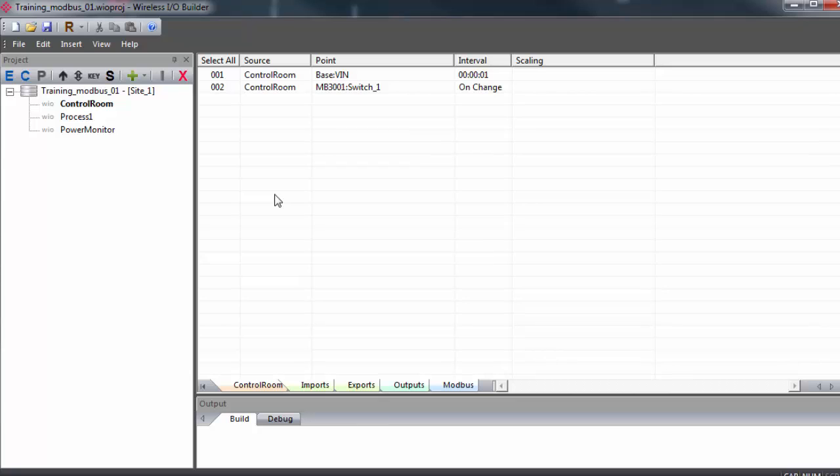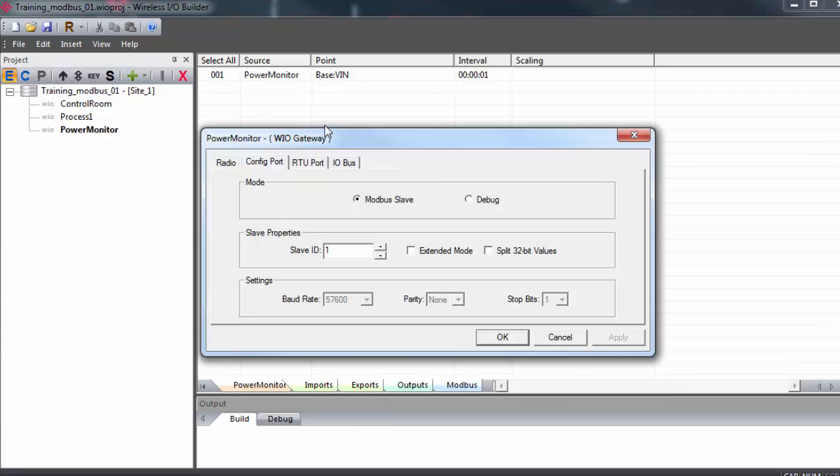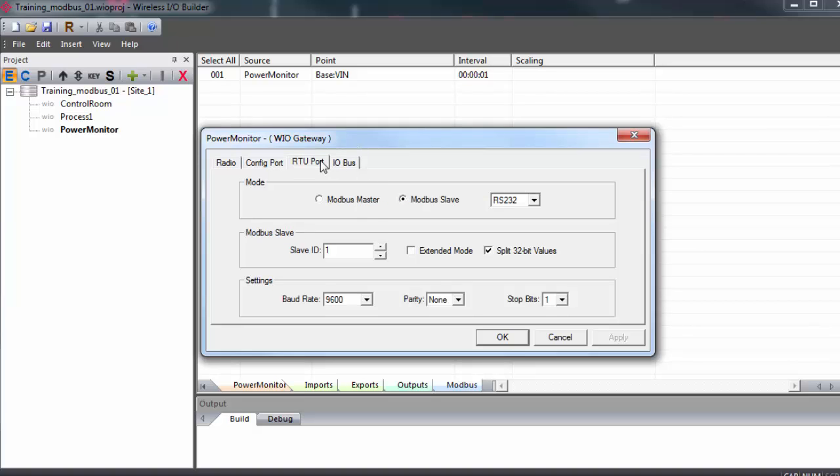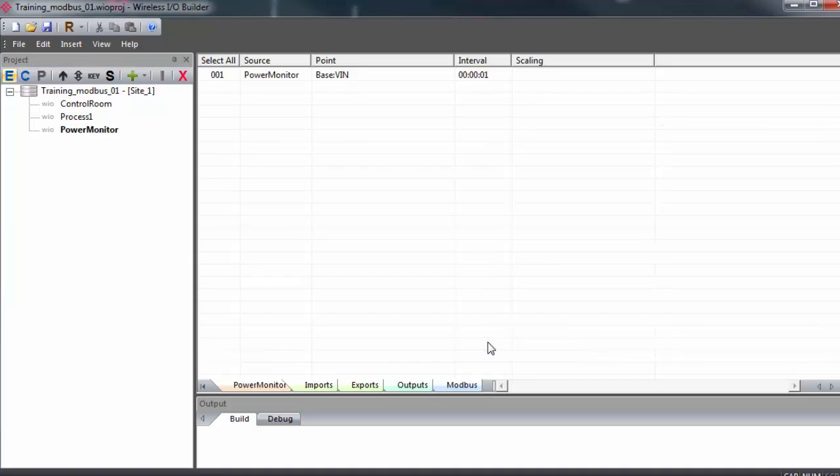This will not interfere with our PLC Modbus Master because they are not connected to each other over the same Modbus network. They are effectively separate Modbus networks. And it's our multipoint wireless I.O. gateways that are actually moving the data between them. So I'll select the gateway and hit edit. And on the RTU port tab, I'll set it to Modbus Master mode. And I have it connected on the RS-485 port. We don't have a slave ID as the master, obviously.